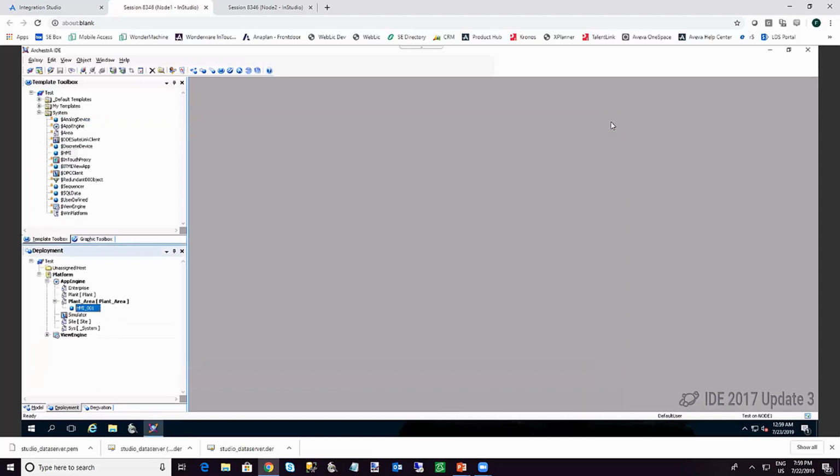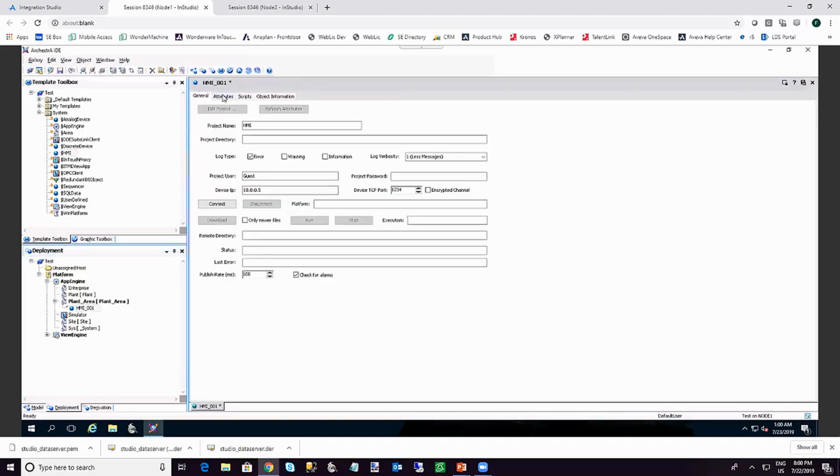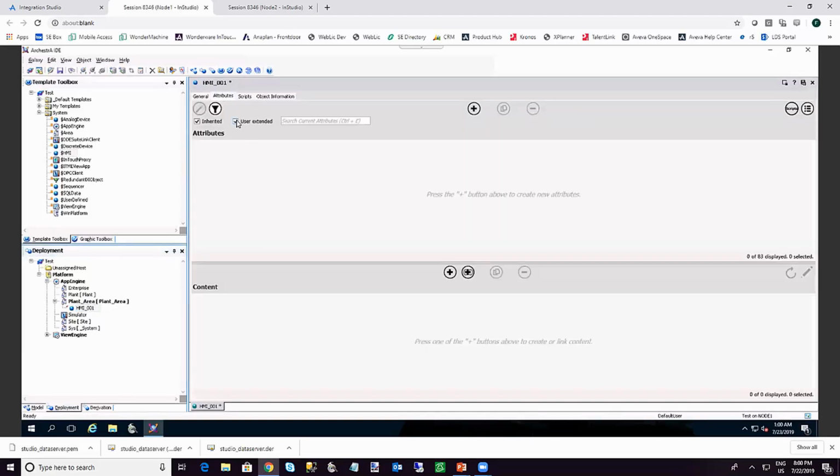So this is the simplest configuration, and you saw that without any scripts and very few clicks here and there, in a few minutes you can completely link a project and tag values from InTouch Edge HMI with System Platform and exchange tag values, timestamp, and quality automatically during the runtime. Notice as well that without any manual configuration in System Platform, if I enable here user extended, all the attributes in InTouch Edge HMI are automatically created as attributes in System Platform just by creating the tags in InTouch Edge HMI and checking the checkbox iValue.